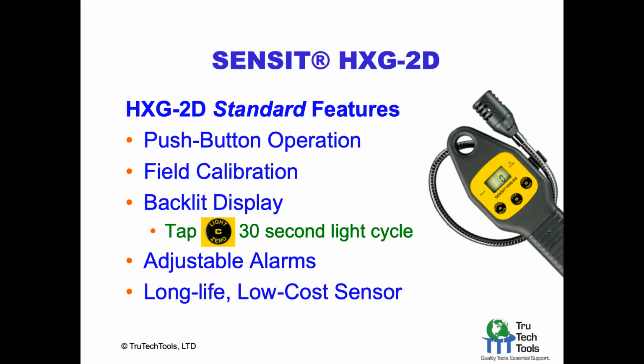The sensor in it is a semiconductor sensor for sensing the gas. We'll talk about it actually a little bit more detail. It is a low-cost sensor. They run about $45. So it's a little bit different than some of maybe the combustion analyzer sensors you're used to, which are usually well over $100 to $200. This is $45 for this sensor.